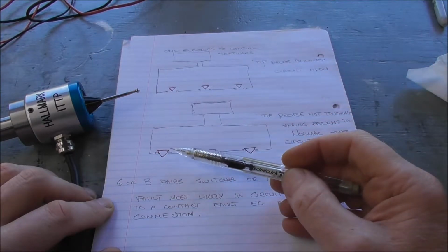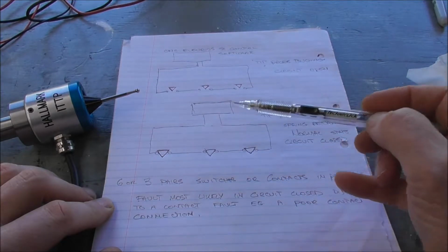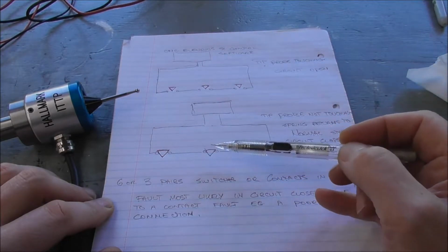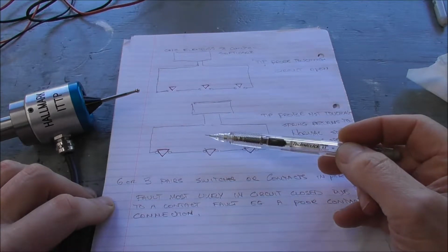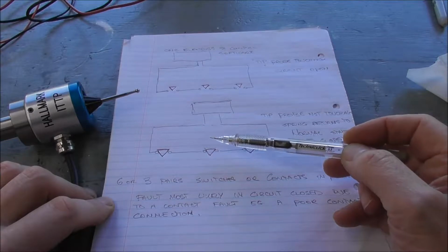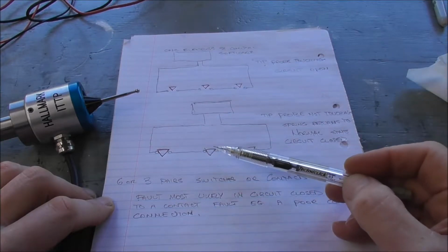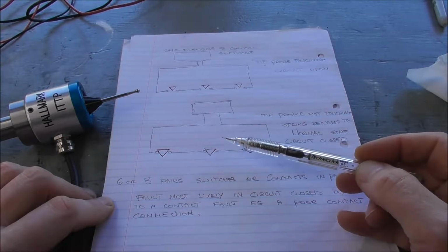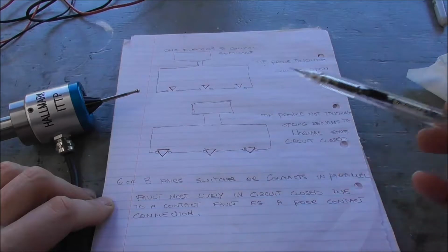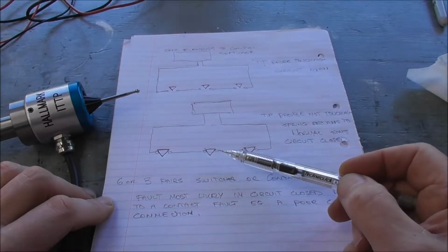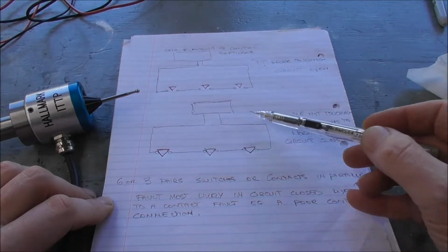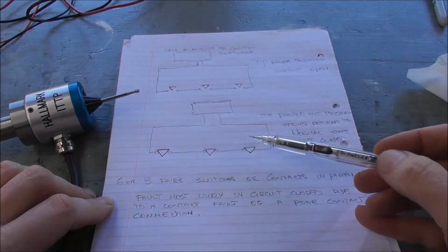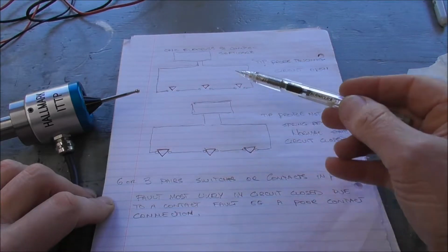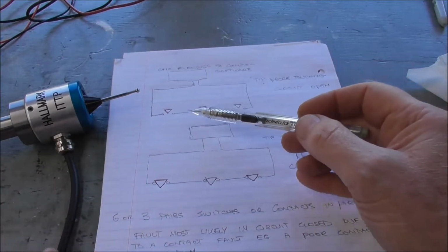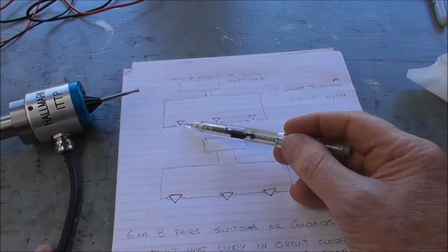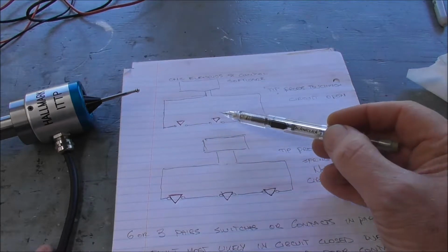So when one of those 6 contacts or 3 pairs of contacts is broken, or the switch is open, then it shows as a trip in the control software. And the normal state, when the tip of the probe is not touching the work, the spring returns the switches to the normal state of circuit closed. So there's continuity of electrical current flowing through the probe. Now when the probe tip touches the work, the circuit is open. And here we're showing these 3 pairs of switches in the open state.